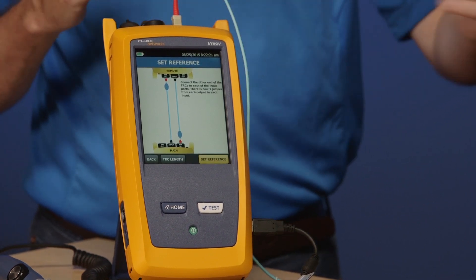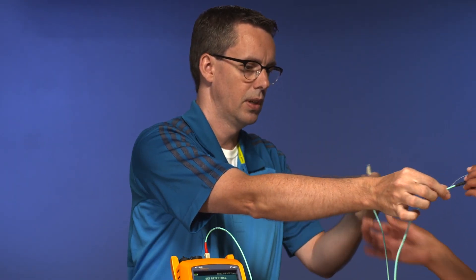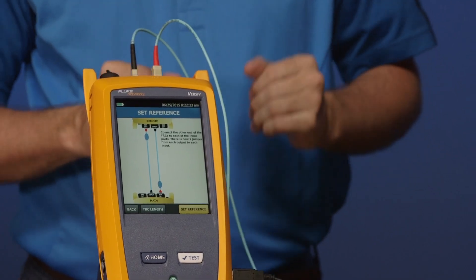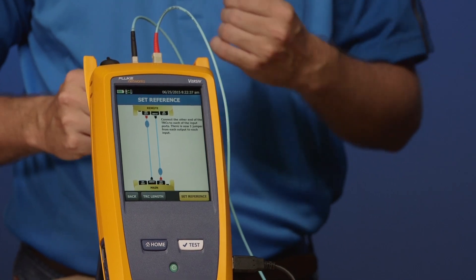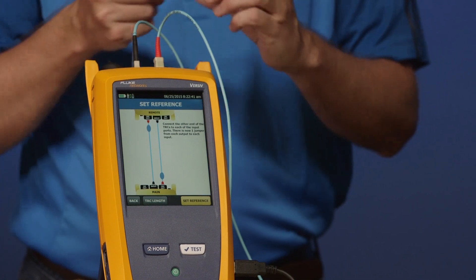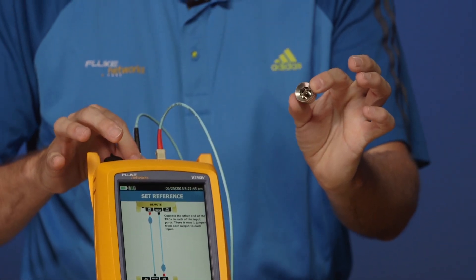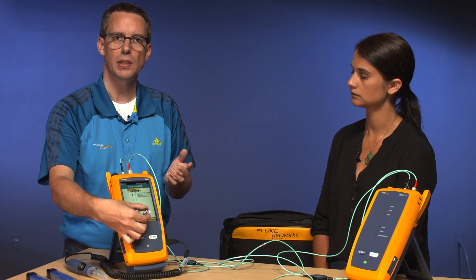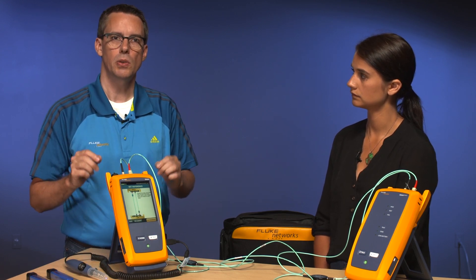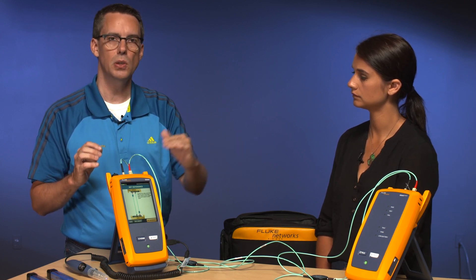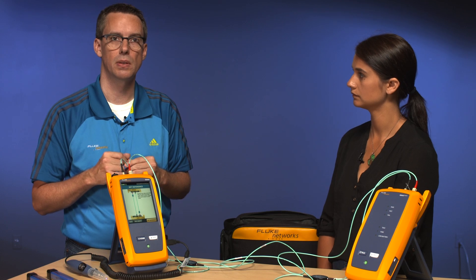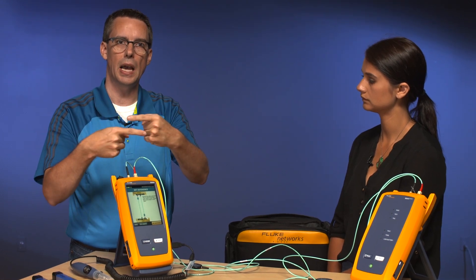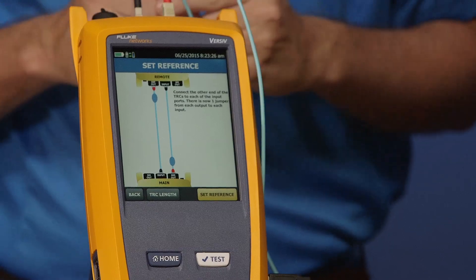The next step is to connect the two instruments together. I'm going to hand my LC connection to you — we'll do a swap at this end and place them onto the input ports. This is LC out of the box with the CertiFiber Pro. If you need to do SC, ST, or FC testing, you can buy hybrid kits for that and change out the inputs. You may have heard the bleep when we connected them — that confirms we got continuity and the polarity is correct between our main and remote unit. In the top left corner of the screen, next to the battery icon, you now see two tester icons with green arrows pointing left and right, telling us the main is talking to the remote.